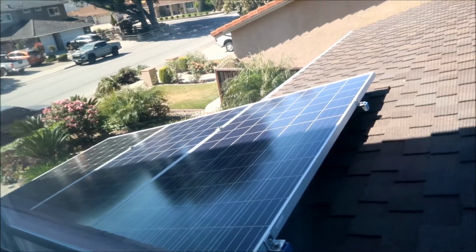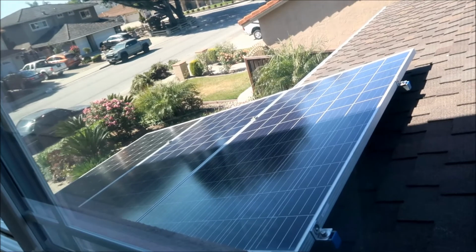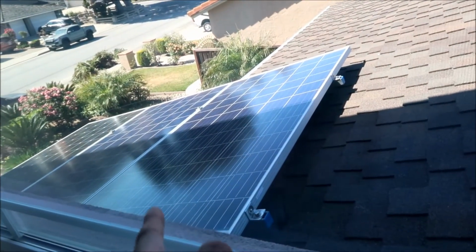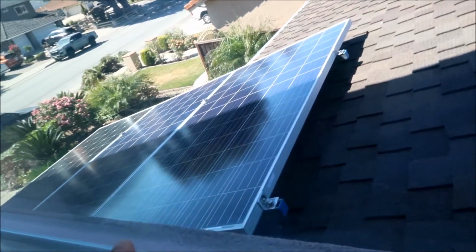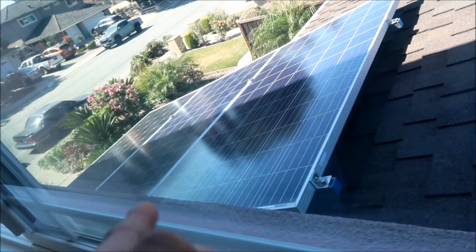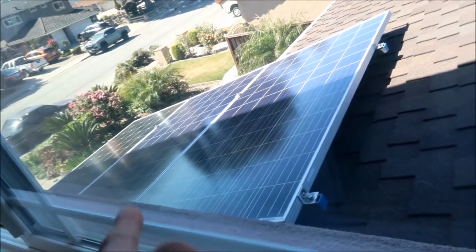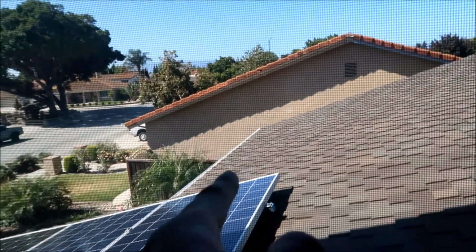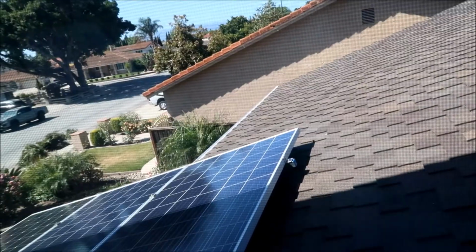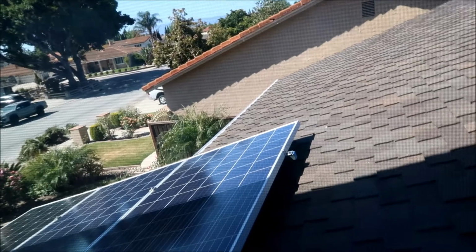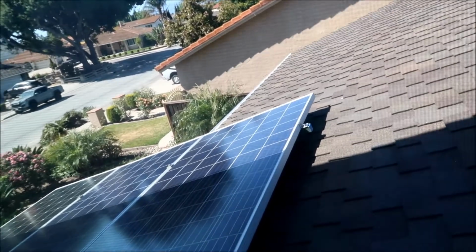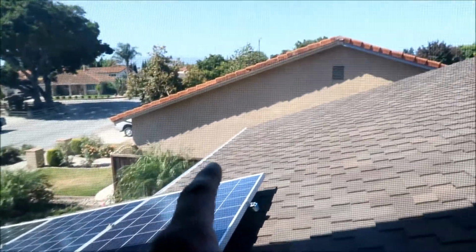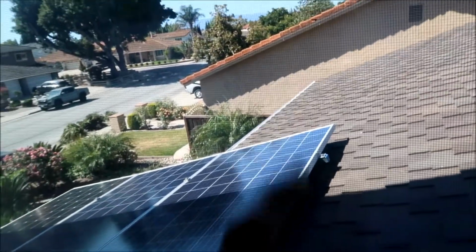So what I'm thinking is buying another 2 or 3 panels and putting them in parallel with this one. That way, in the morning, these don't really make any power, but if I put panels over there, they'll make power all day, pretty much. That's the only way we could really get around this. So I thought putting it in parallel would help, but it won't. The best thing to do would be to just move it over there, I guess. But these won't fit over there, I think.